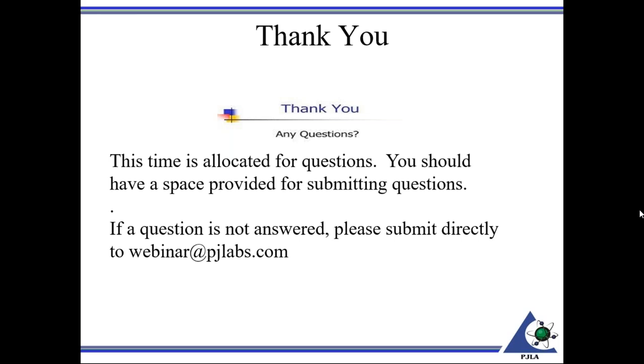And as stated, if this is going to be considered an internal type employee, look at our policy on traceability under in-house calibration. Basically, it's handled just like an accredited calibration, except it's not listed on the scope. So we would look at the competencies of the individual with calibration. Uncertainty is going to be different than if you're a testing person, but we would check that it's established, that it's reasonable, and that appropriate methods are being used. So it would be assessed just like a regular calibration. I hope I answered your question there. I know I went around in a little bit of a circle with a couple different things.